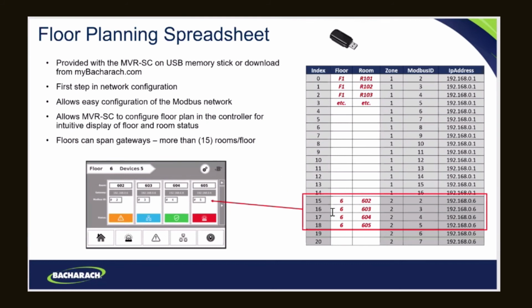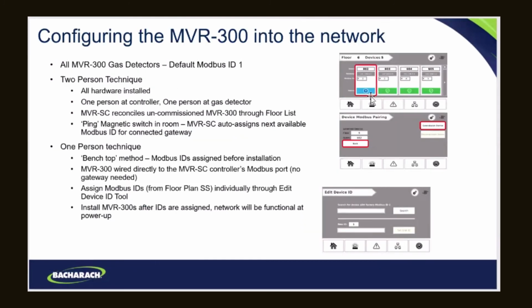This is a typical configuration. You can see here we're on floor 6. We have rooms 602 through 605. It'll show you what zone you're in. Typically, that's what gateway you're going through, and it'll show you the address. That is repeated in the floor view, and if this has already been commissioned, it'll show you the status of what that Modbus ID is currently, or it will show you something like this, where it is suggesting that that ID has not been commissioned yet. And that will cause the system to say, hey, this is an ID 1, it needs to be commissioned, let's go ahead and move through that commissioning.